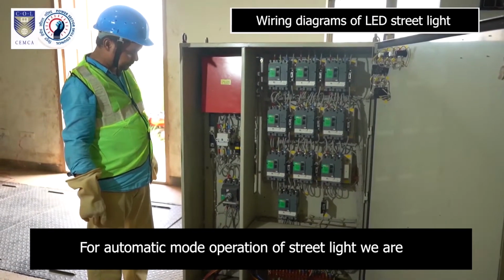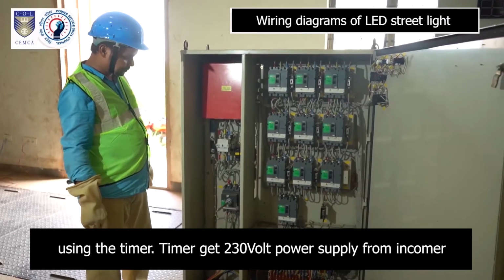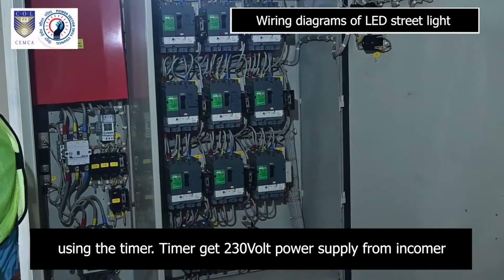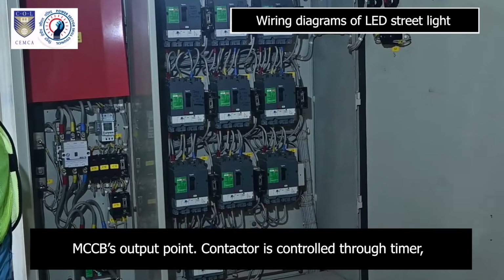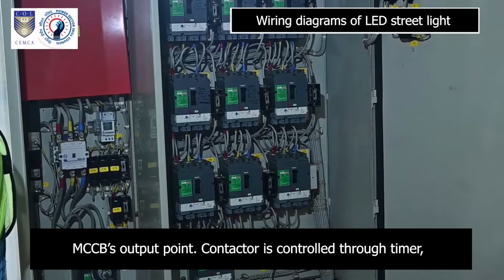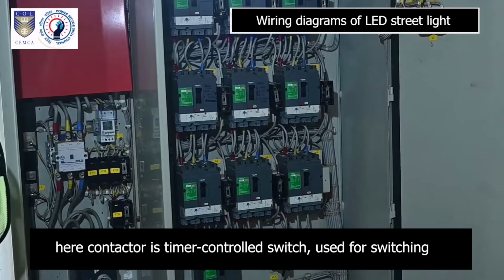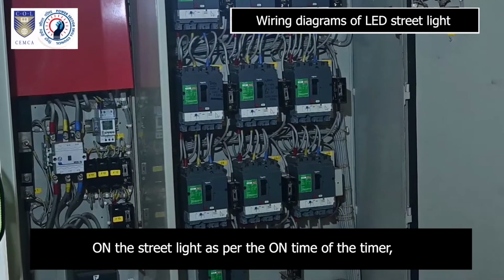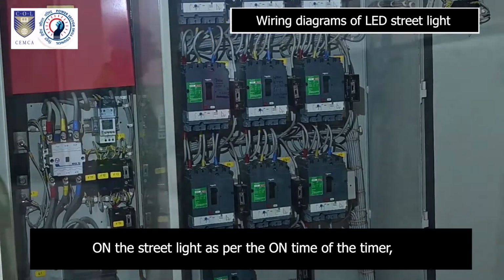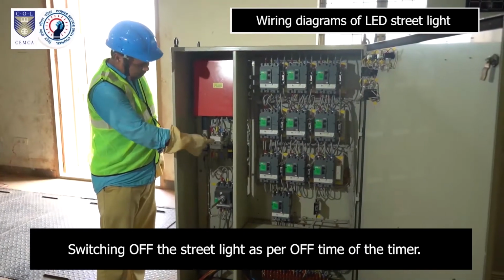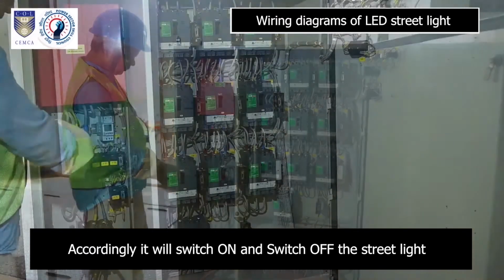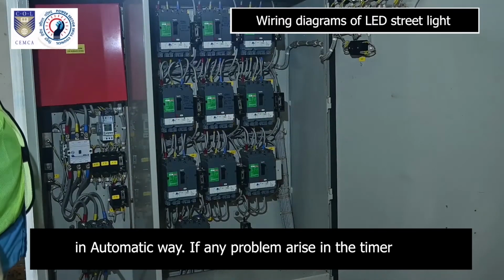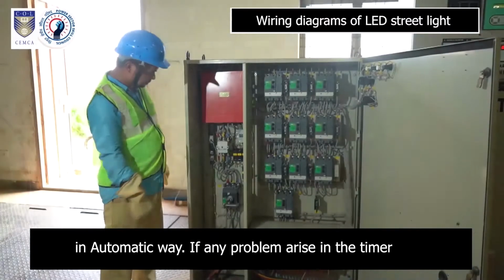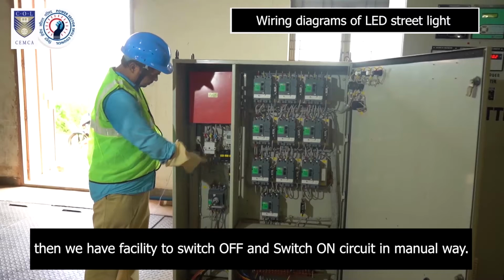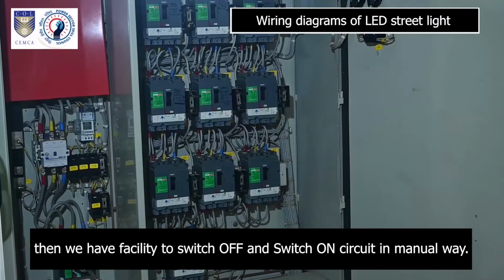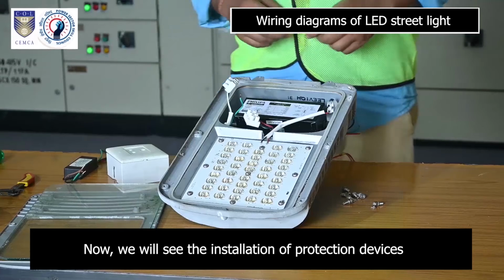For automatic mode operation of street light, we are using the timer. Timer gets 230 volt power supply from incomer MCCB's output point. Contactor is controlled through timer. Here contactor's timer controlled switch is used for switching on the street light as per the on time of the timer, and switching off the street light as per off time of the timer. Accordingly, it will switch on and switch off the street light in automatic way. If any problem arises in the timer, then we have facility to switch off and switch on circuit in manual way. Now, we will see the installation of protection devices.